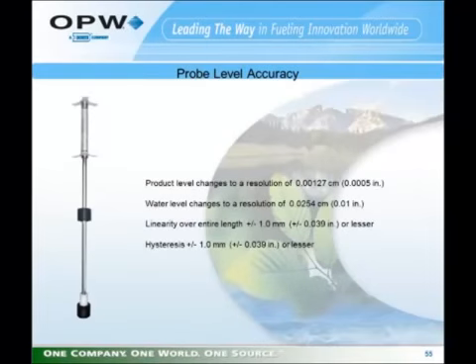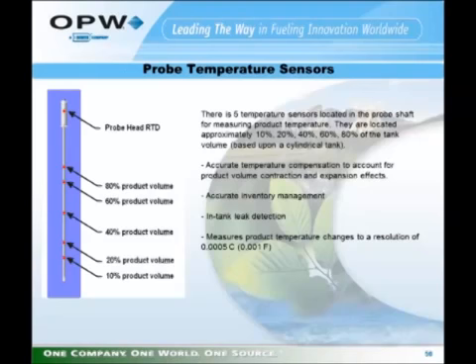Accuracy of the probe is down to 0.0005 inches. Water level changes to a resolution of 0.01 inches. Linearity, hysteresis, those are engineering terms not normally used by technicians in the field. They're given to you here so that you can see if you are bidding with a specification that's been introduced into the bid process. You can compare this equipment to competing equipment.